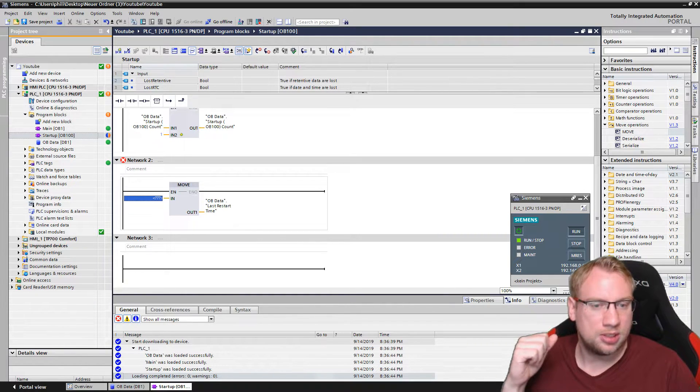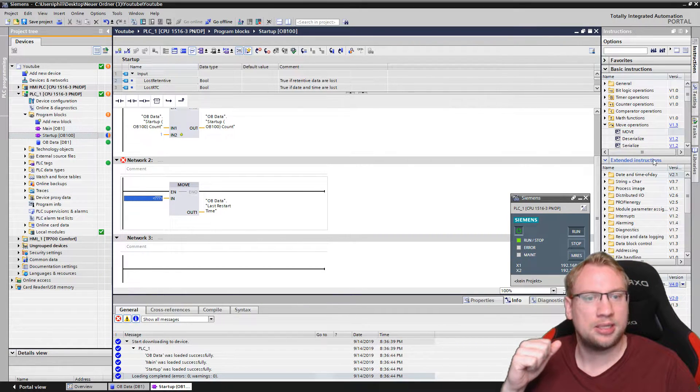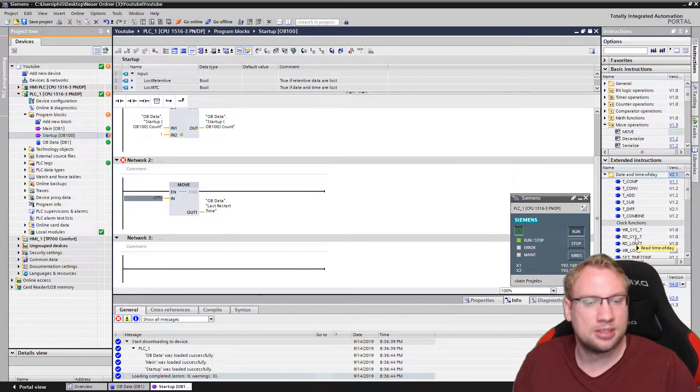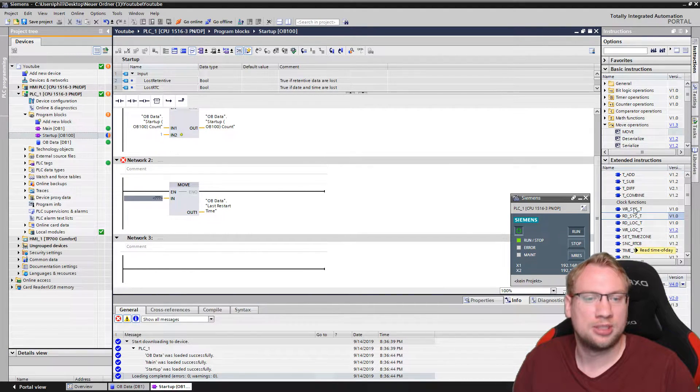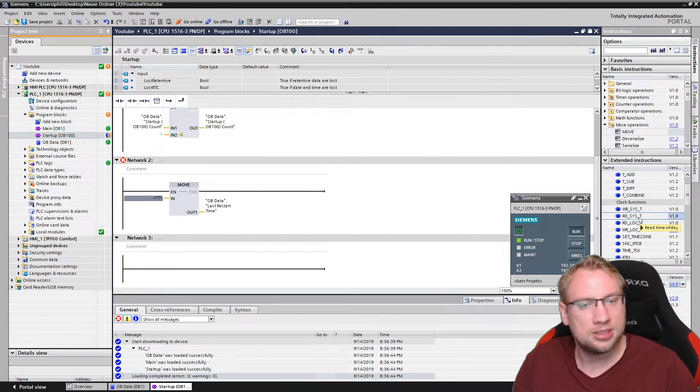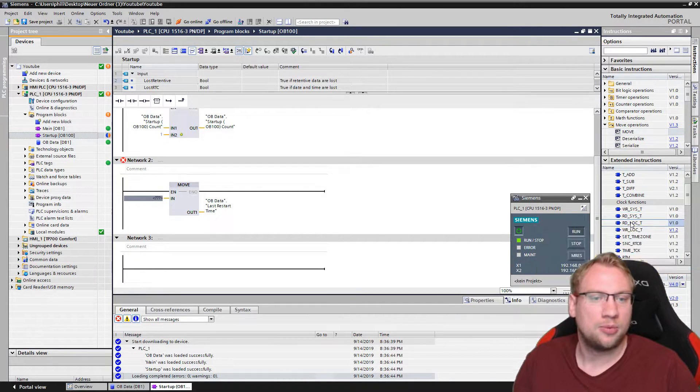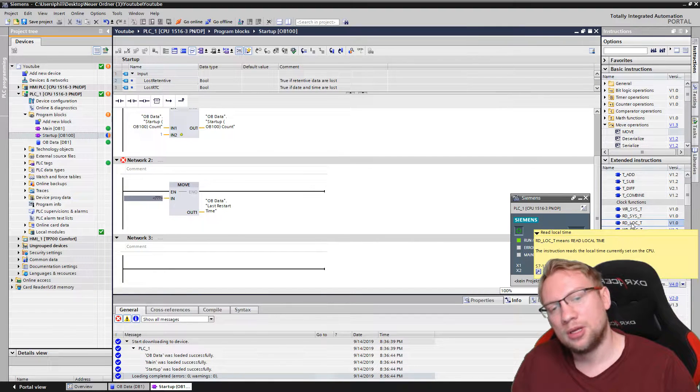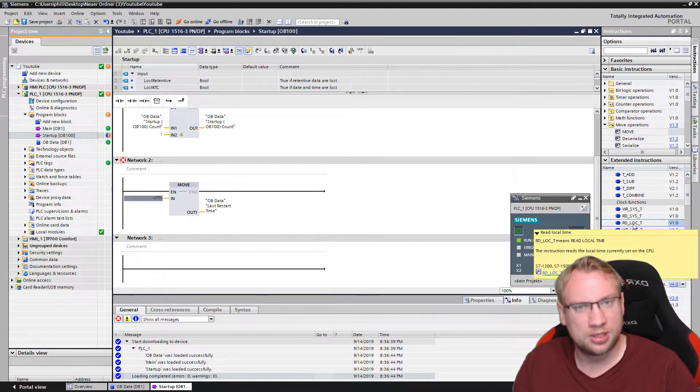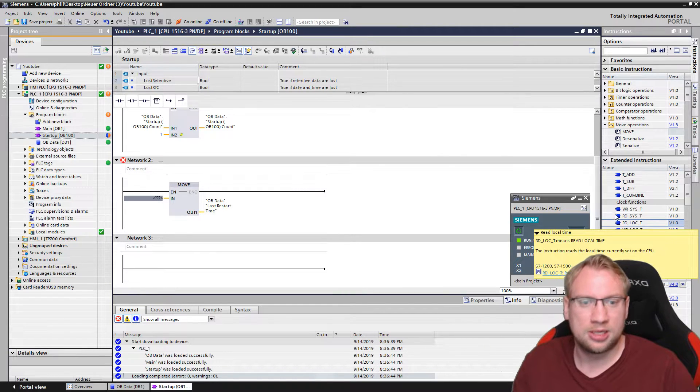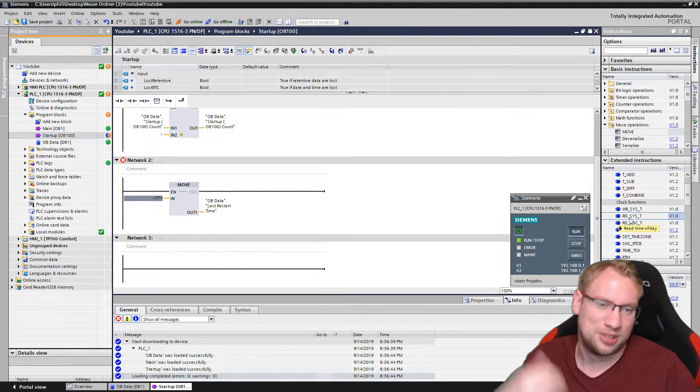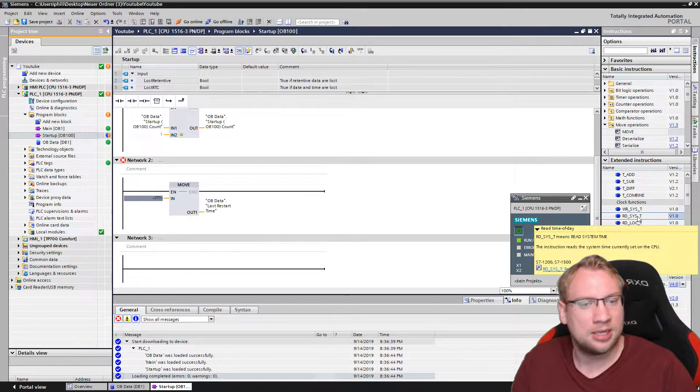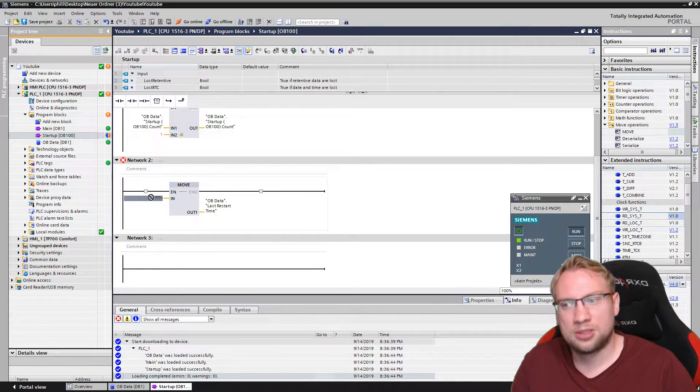There is a block down here, somewhere there, extended instructions, date and time. We can actually read the system time inside the PLC. We have system time, RD_SYS_T, read system time, and we have RD_LOC_T, read local time. Local time is with summer time, so plus one hour, and winter time minus one hour. I want the system time, so really without any summer time. Let's put this in.